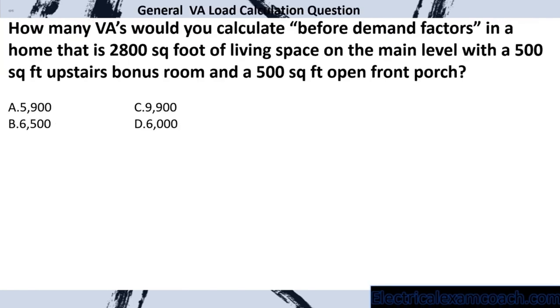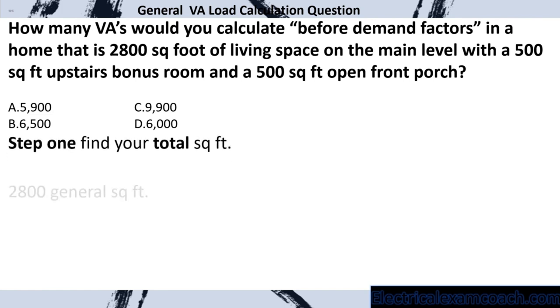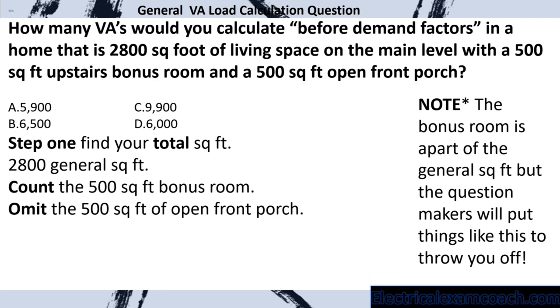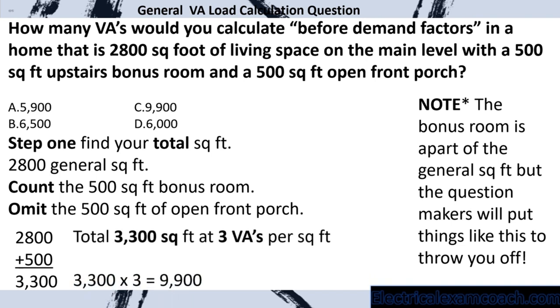How many VAs would you calculate before demand factors in a home with 2,800 square feet of living space on the main level, a 500 square foot upstairs bonus room, and 500 square feet of open front porch? First, total the square feet. We count the 2,800 general. We count the 500 square foot bonus room — note that question makers will put things like this in your test to throw you off. We omit the open front porch. That gives us 3,300. We take 3,300 multiplied by 3 VAs per square foot, and we select C.